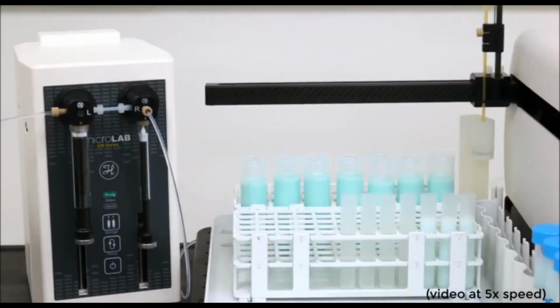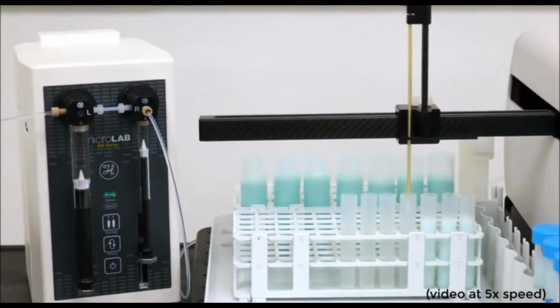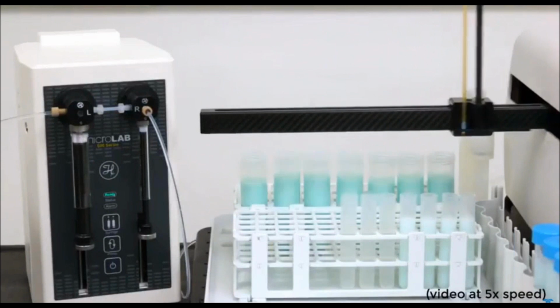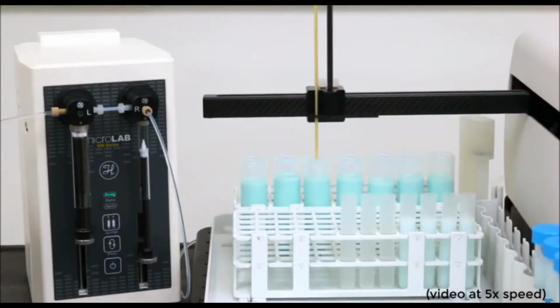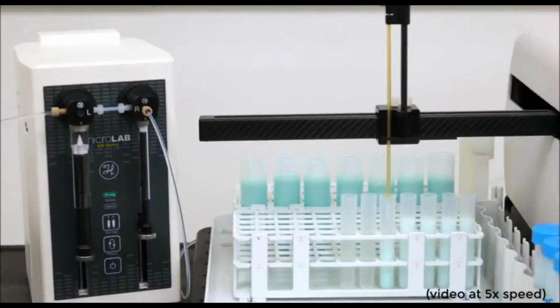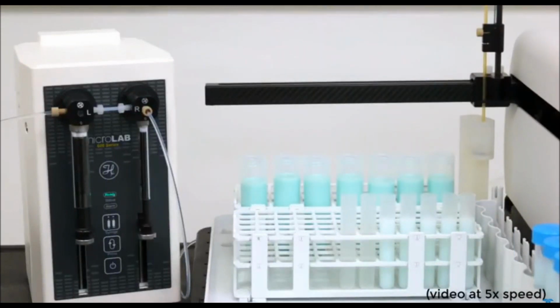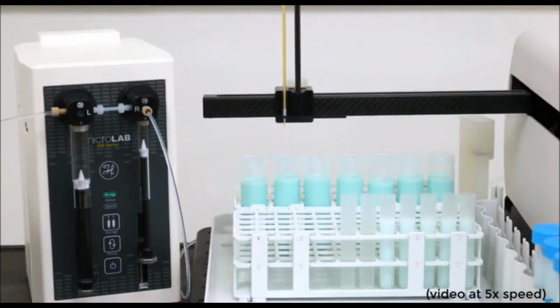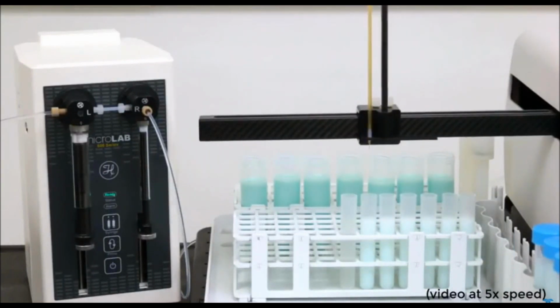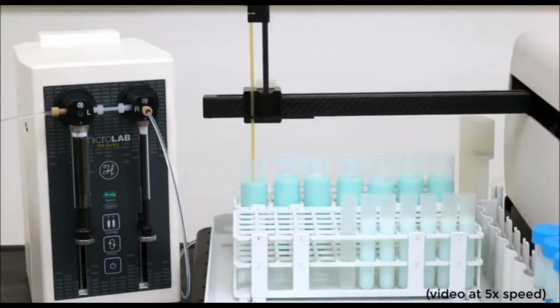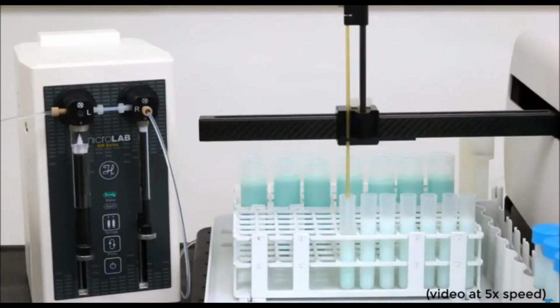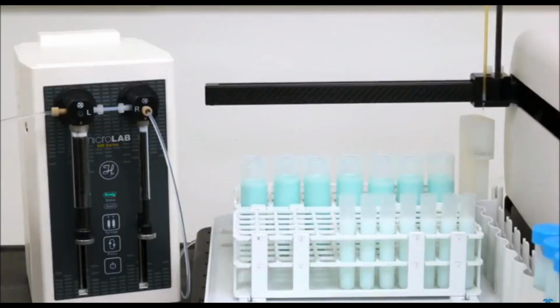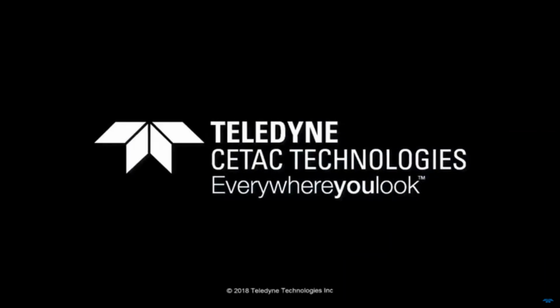So now the video has been sped up to 5x speed. But it provides a nice visual, and you'll see, as well as you can on the video, that the samples come out side by side, pretty much identical, which is what we're hoping to see. Also, you may notice that the sample probe goes down to different depths in the different tubes, and that's by default. It has a default depth of 110 millimeters for your raw sample that it's pulling up, and 80 millimeters when it's dispensing. That way it keeps the probe out of your final sample to preserve the integrity of the data as much as possible.